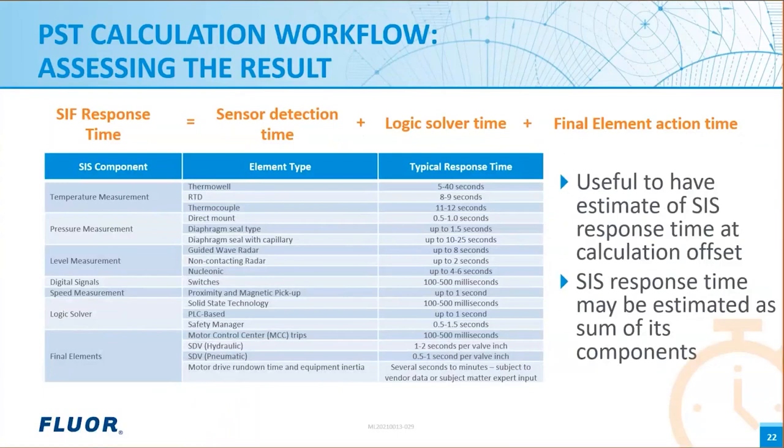So we work that out by summing these three components. The safety instrumented system response time is the sensor detection time, plus the logic solver time, plus the final element action time. Many of us might be familiar with the idea on final elements of allowing, say, one second per inch of valve body. And usually if you've got a pressure trip, for example, the valve closure time or activation time is usually very long compared to the sensor detection time and the logic solver time. So those terms tend to get ignored.